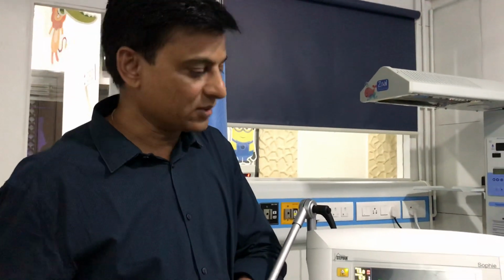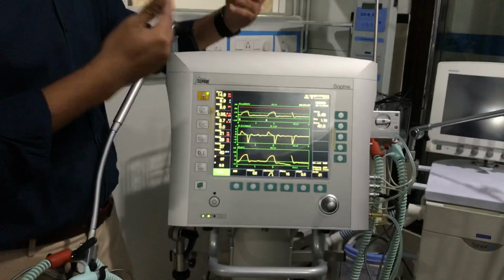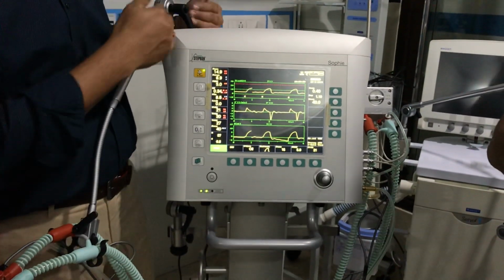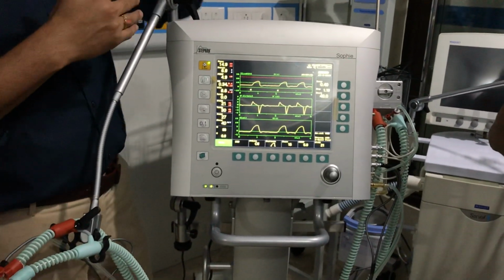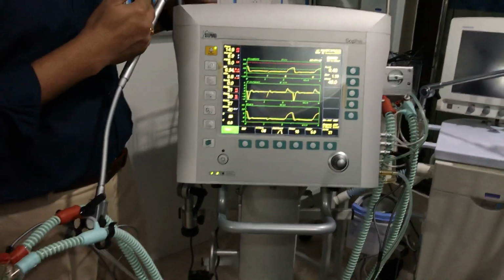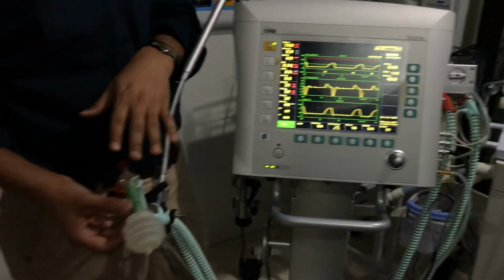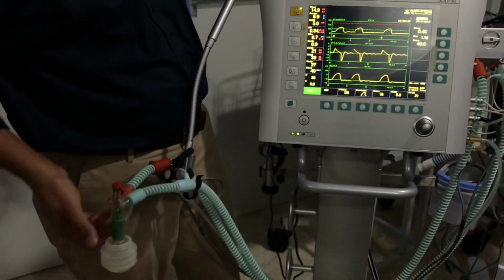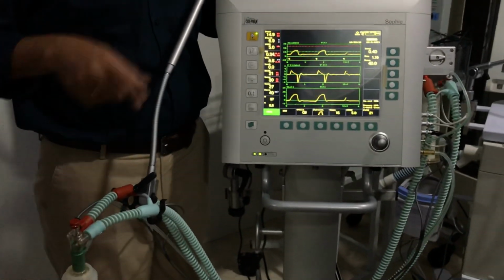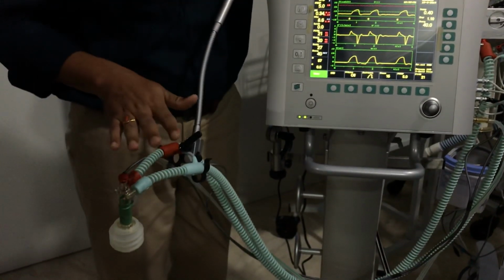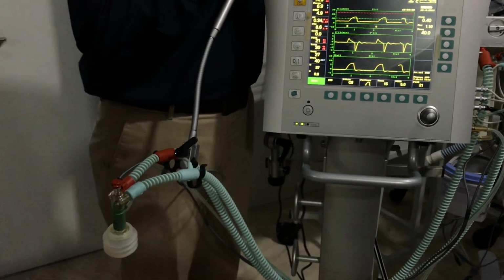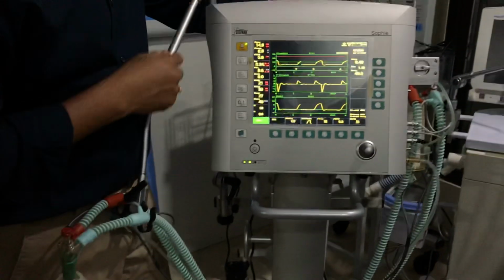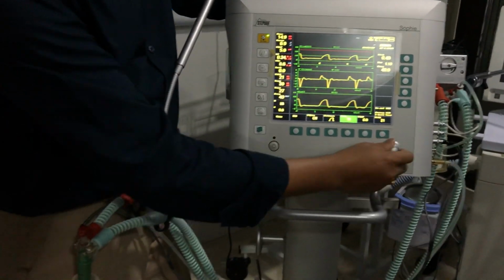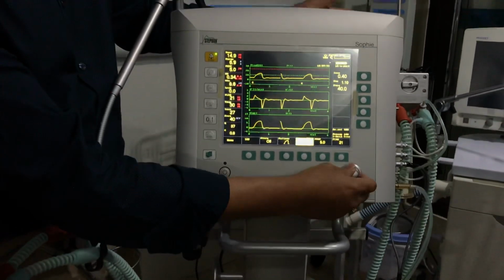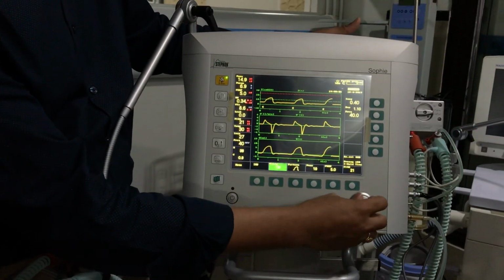If you are going for HFOV, you have to change the flow sensor again from conventional to HFOV, because flow in HFO is quite high compared to conventional. So by default, we are giving C type. Since you used it in PGI, that's the reason I am giving the explanation. Otherwise, we don't go in depth like this. So all these set parameters, anytime you can change them.